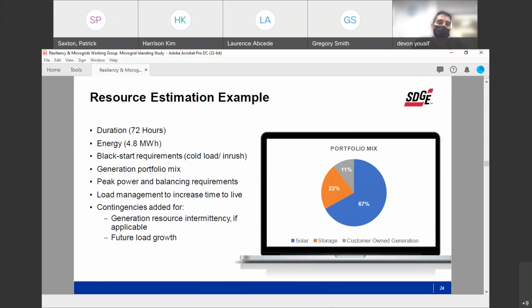How long will it take to keep up that duration for? Will you need to incorporate other resources? This is just an example of 4.8 megawatt hours—in terms of battery, how much capacity the battery can store. This basically helps you create your generator portfolio mix and determine how much solar, how much battery you need. During the day, we're going to need the solar to cover our load and charge the batteries overnight if we plan on doing something for 72 hours, or oversize the battery—whichever makes more sense for the scenario you're dealing with.